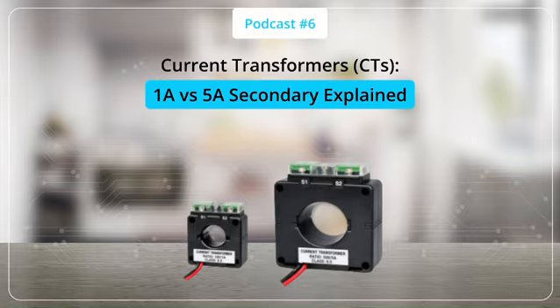Now, let's understand when to use a 1A CT and when to use a 5A CT. A 1A CT is generally the better choice when the distance between the CT and the measuring device is long, typically beyond 100 meters. It is widely used in modern digital systems, smart grids, and large substations where minimizing losses is important. On the other hand, a 5A CT is more suitable for shorter distances, usually under 20 meters. It is commonly used in older systems and industrial environments where durability is more important than precision.